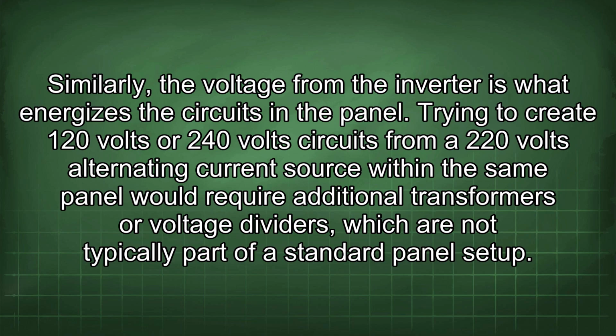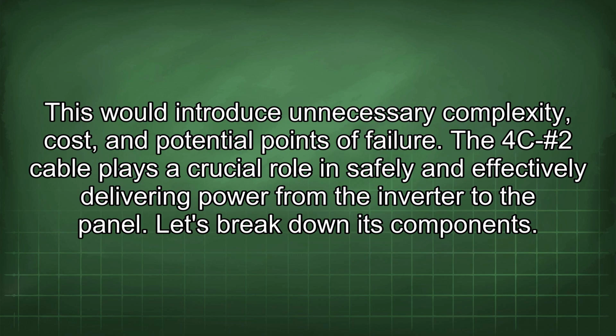Trying to create 120 volt or 240 volt circuits from a 220 volts alternating current source within the same panel would require additional transformers or voltage dividers, which are not typically part of a standard panel setup. This would introduce unnecessary complexity, costs, and potential points of failure. The 4C-2 cable plays a crucial role in safely and effectively delivering power from the inverter to the panel. Let's break down its components.